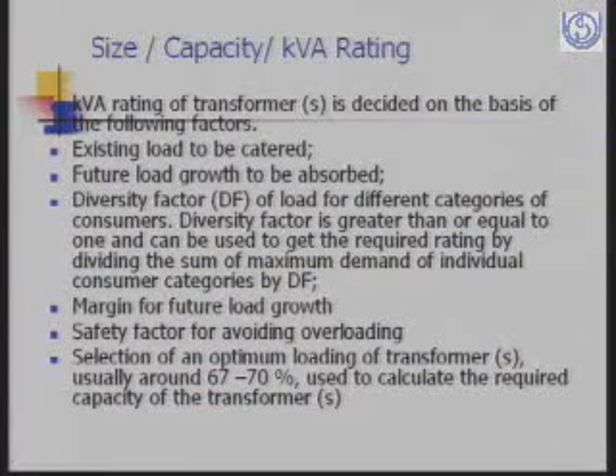So we need to consider the diversity factor while computing the rating of the transformer, the margin for future load growth, and safety factor for avoiding overloading. And usually we select a transformer and its rating such that the transformer is loaded up to 67 to 70%. It is not loaded more than that. It has been observed generally that our transformers are loaded more than 100% and they are failing because of the overload. But actually when we plan our system, then we should not load the transformer more than 70% to get optimum efficiency of the transformer as well as to prevent failure of the transformer.